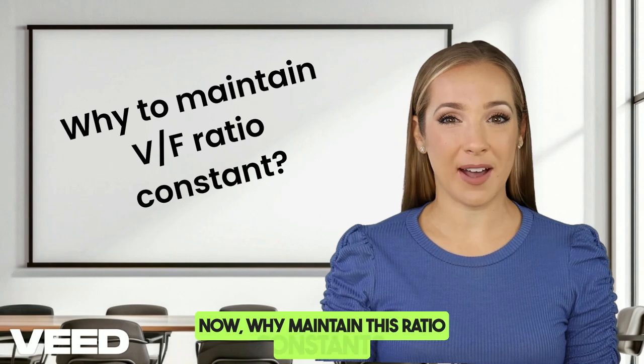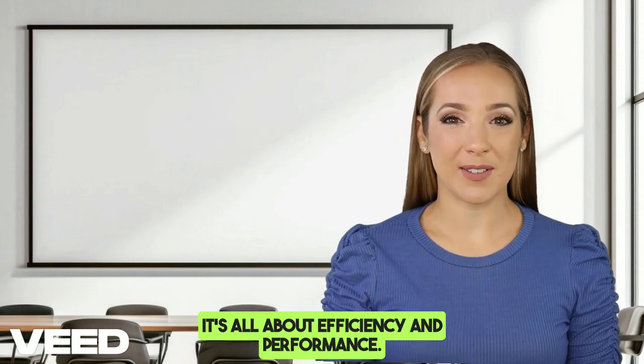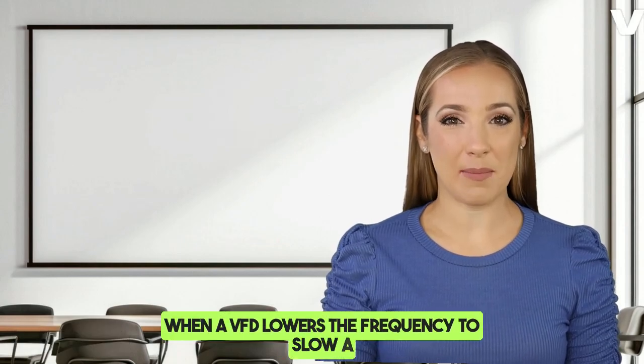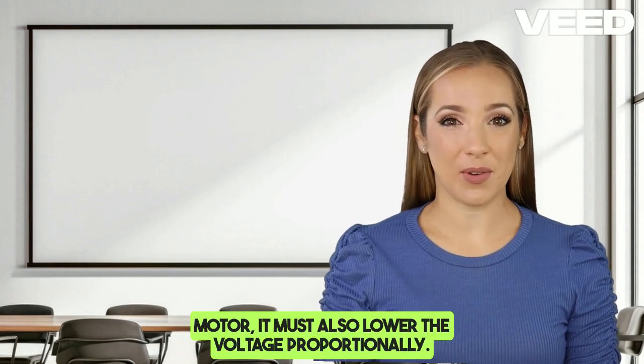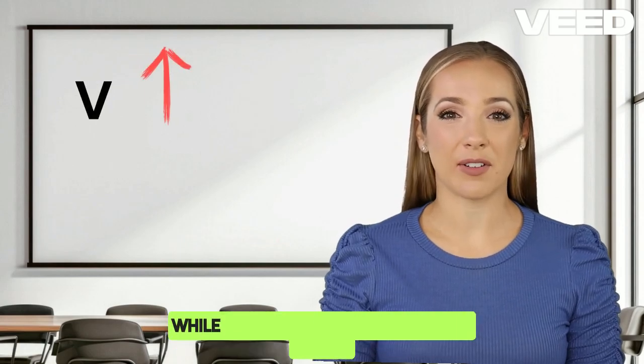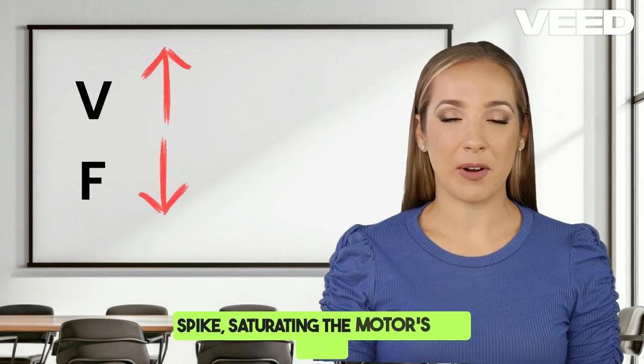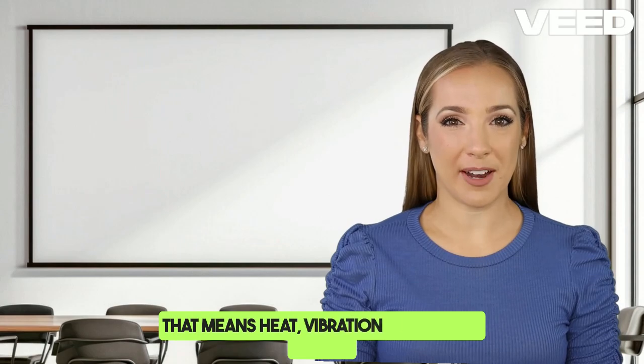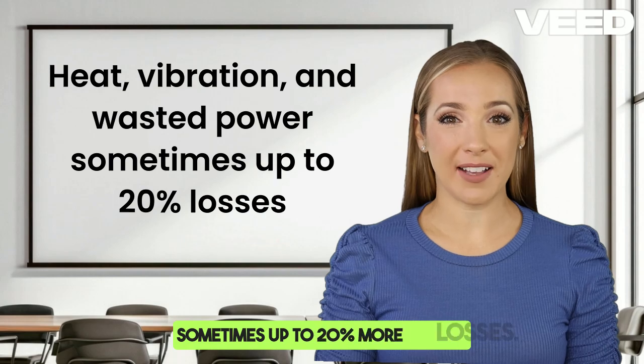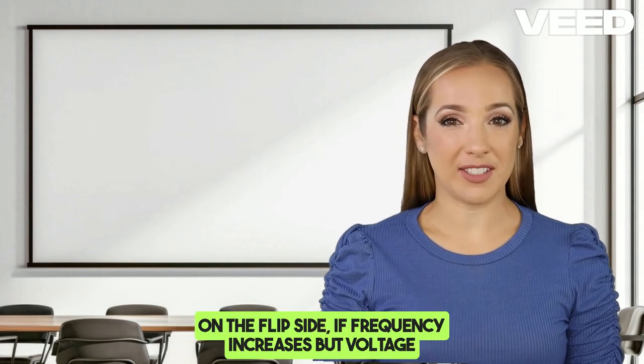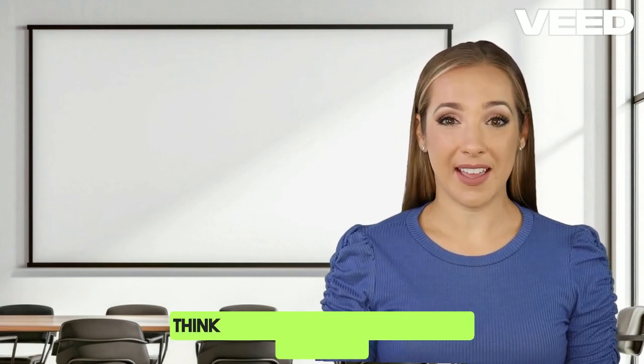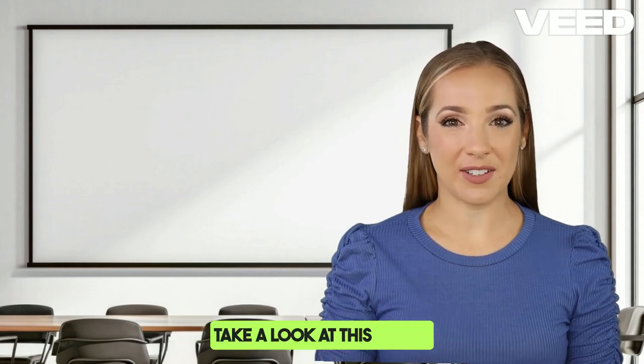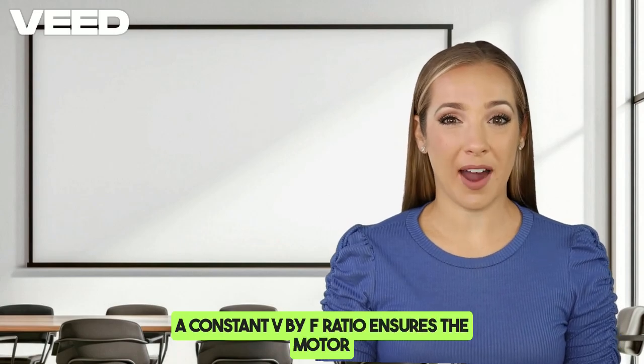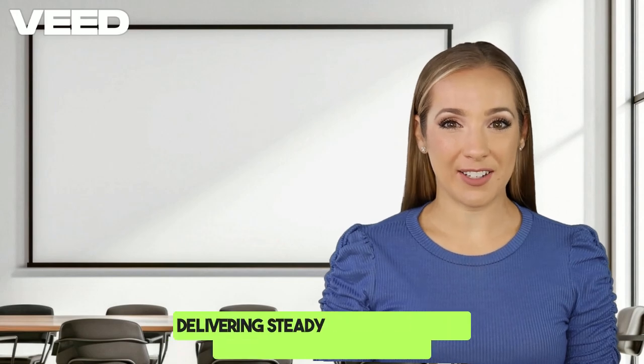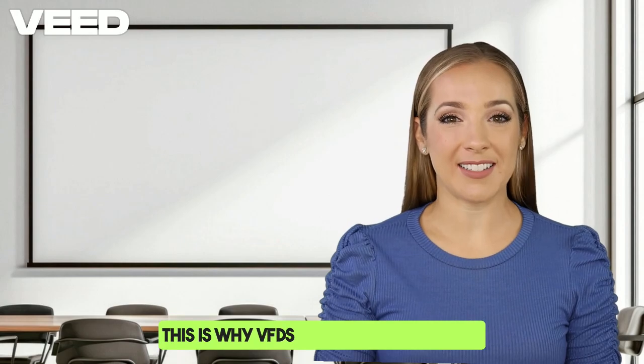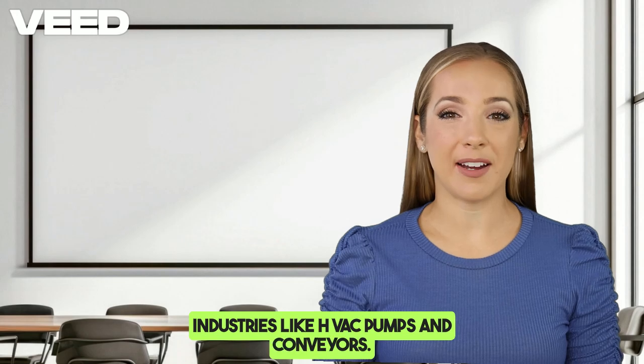Now, why maintain this ratio constant? It's all about efficiency and performance. When a VFD lowers the frequency to slow a motor, it must also lower the voltage proportionally. Why? Because if the voltage stayed high while frequency dropped, the flux would spike, saturating the motor's iron core. That means heat, vibration, and wasted power, sometimes up to 20% more losses. On the flip side, if frequency increases but voltage doesn't, the flux drops and the motor loses torque. Think of a car engine sputtering at low RPMs. Take a look at this graph. A constant V by F ratio ensures the motor operates in its sweet spot across all speeds, delivering steady torque without overheating or stalling. This is why VFDs are game changers in industries like HVAC, pumps, and conveyors.